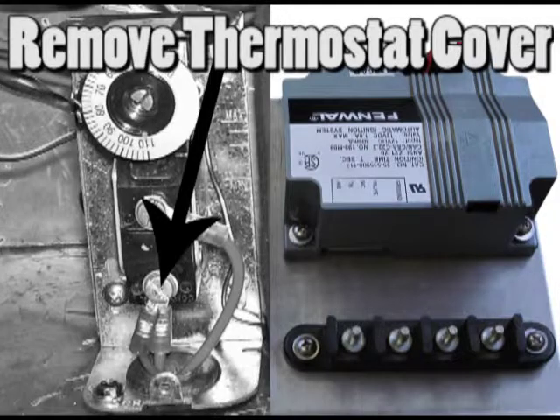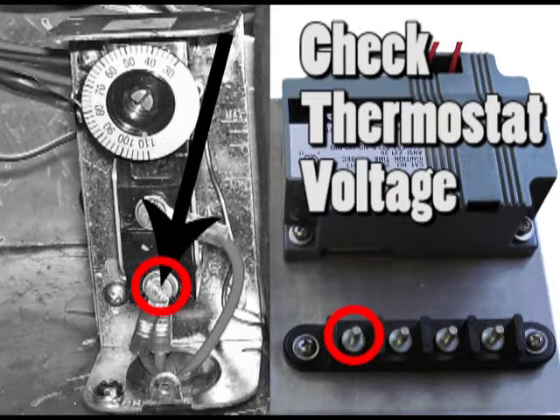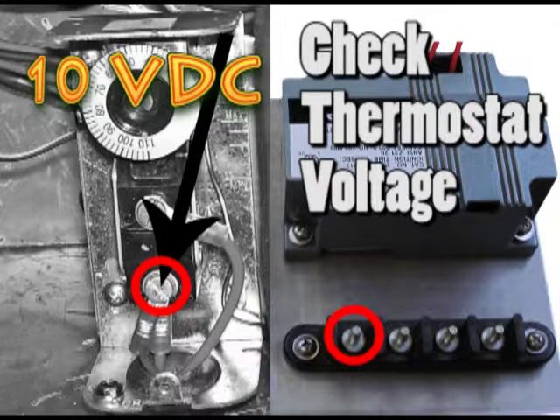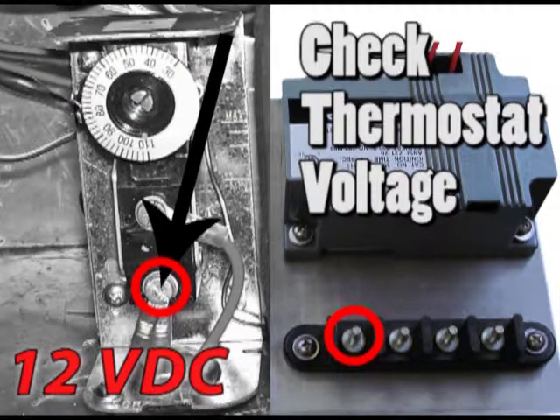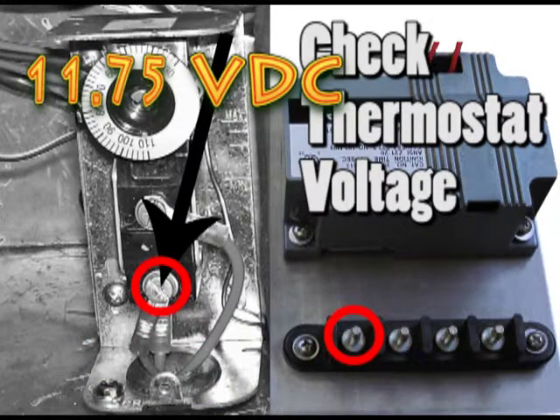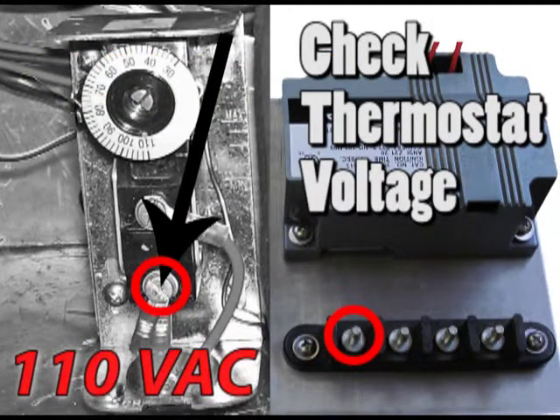Remove the cover to the thermostat and check that the heater is receiving at least 10 volts DC if hooked up to the 12 volt DC battery power, and at least 11.75 volts DC when powered by the 110 volts AC wall socket power.